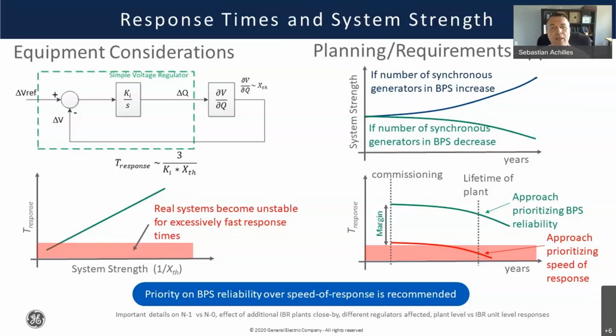Looking at it from the planning or requirement approach on the right side of the slide, we try to reflect that system strength behaves differently now across the planning horizon. We were used to systems behaving like the blue line, where system strength increases over the years because we add more generators to the grid—generators meaning synchronous machines.